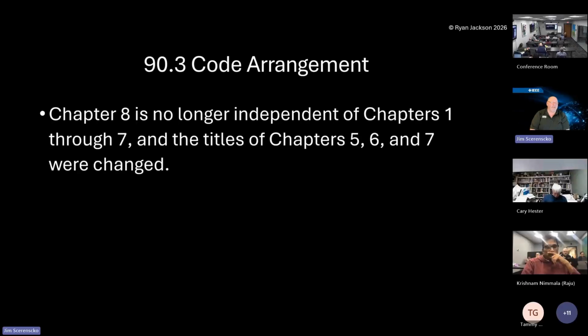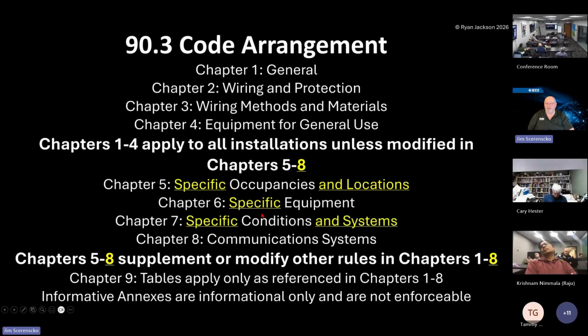If you go back and read it, it used to say chapters 1 through 4 were general wiring and conditions, and then 5, 6, and 7 were special equipment, special occupancies, and emergency systems. And then Chapter 8 all stood by itself. It used to say that chapters 1 through 7 can modify anything in 1 through 4, and so on and so forth. But it never included Chapter 8. Chapter 8 always said you only had to do this if it was called out specifically in Chapter 8. Well, that's all changed, because now Chapter 8 is part of the code.